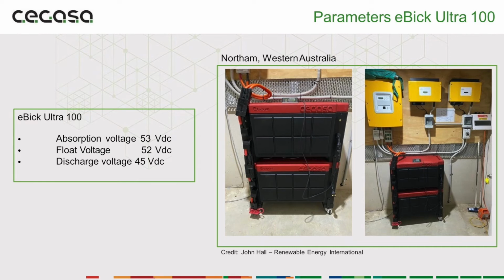I'll show you an example. This is the very first system that we installed in Australia. It was a client of BayWa. Well, in this case, obviously, it's no communications, with SMA Sunny Island. Very similar to what I commented before with the other batteries, because when you play them as unmanaged, at the end they are similar concept with different capacities, but they work exactly the same. You just need to know the values, set them on the inverter, and then you connect.